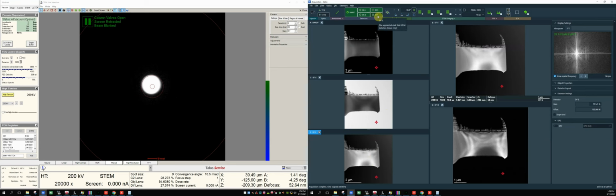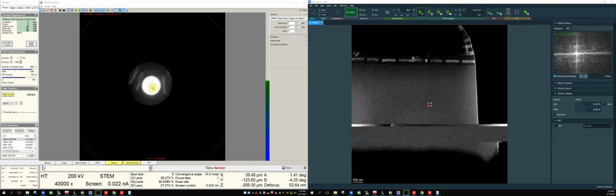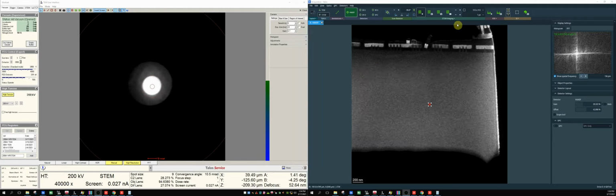Good. So now we can head for the high resolution. For this, I will just disable the other imaging modes and start searching. To be able to perform the high resolution STEM imaging, we need to find somewhere which is close to zone axis. So now you can see, using the Flucam to see the diffraction pattern and judge where is the best for the zone axis. Okay, let's see. I can pause the scan on blank beam and position, park the beam to a different area, see where I end up with the best.